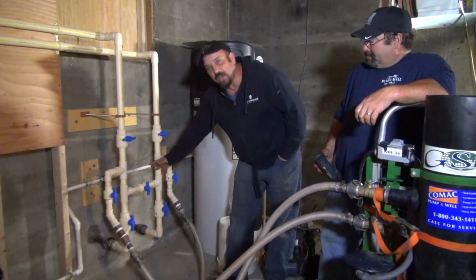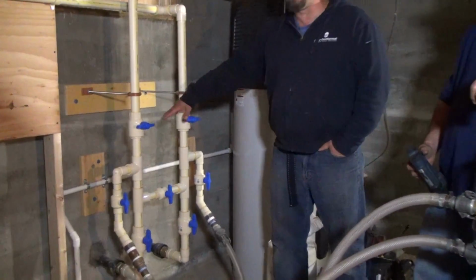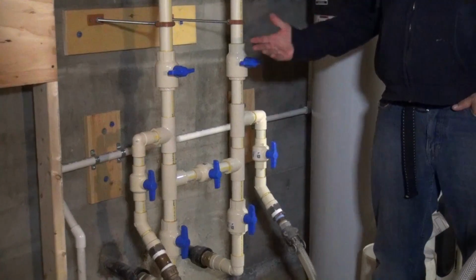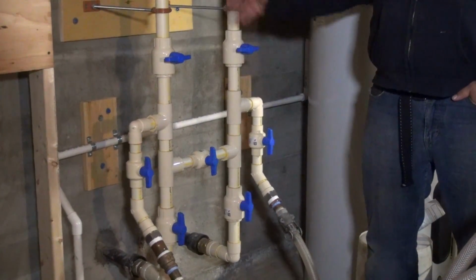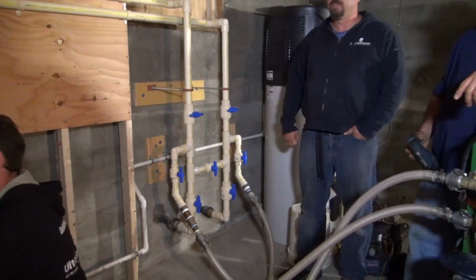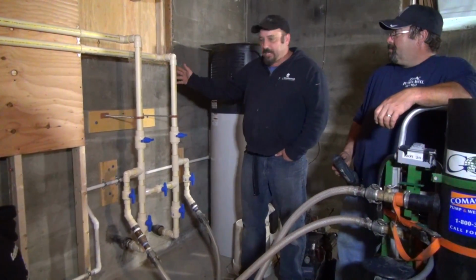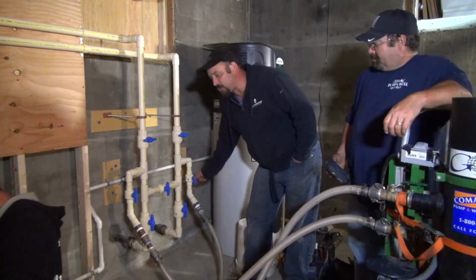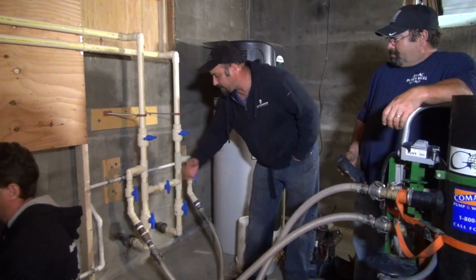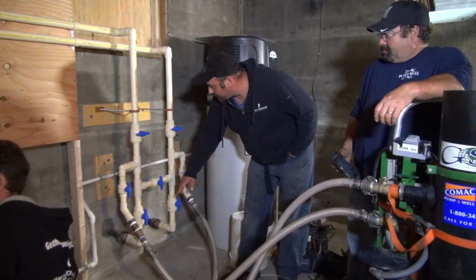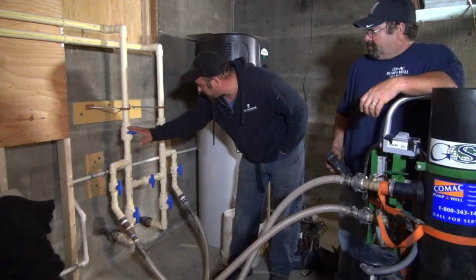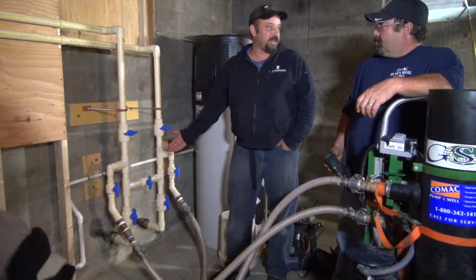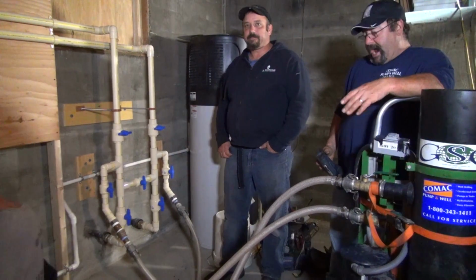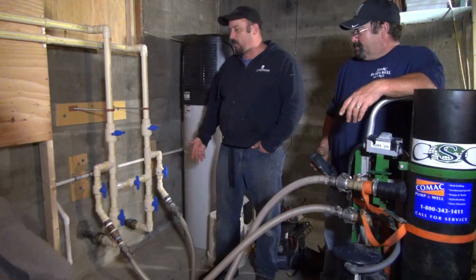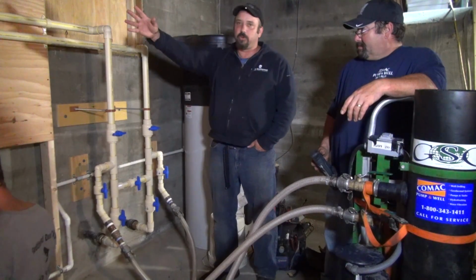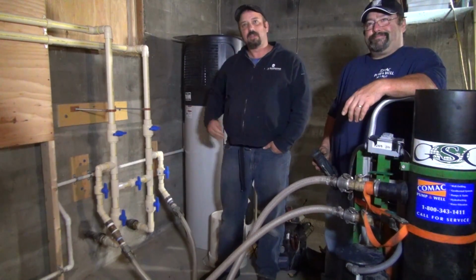So everything here is now in process with the pump running. Everything's in the process of filling up the loop field. Eventually, Bill's going to have water coming into the building here, and then we're going to be able to add glycol, mix it all up, and filter it throughout the whole system. Not much to explain here other than we have an inlet and an outlet, and a couple of purge ports for the pump cart to come into, to move fluid in and out. So with this being shut here, and this being shut here, you're just filling the field right now. Right, just bleeding all the air out and adding water to get full water. Yep. And then once we get to that point, the valves will get opened up, and the fluid solution will then be filled into the heat pump system and connected fully with the field.